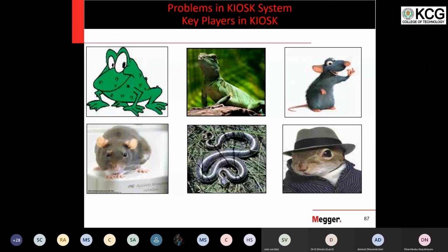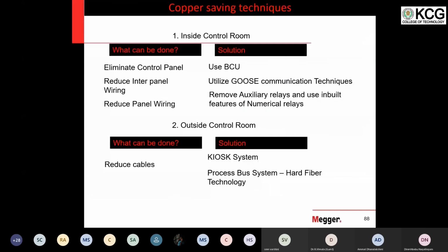Therefore, any system or technology which is not providing the comfort that we expect is actually not a successful one. So during the time of theoretical implementation, this was a perfect solution. But after practical installation, the real life problems came in, and because of this, we were forced to move to a different technology. So that's where the kiosk system failed, and we moved to a different technology. That is the process bus technology.